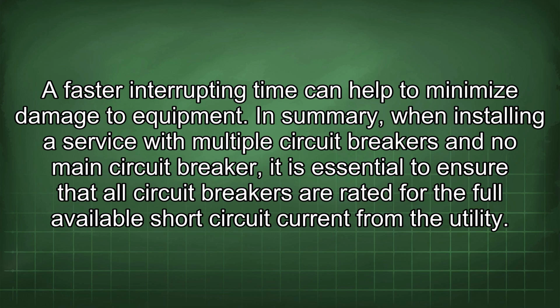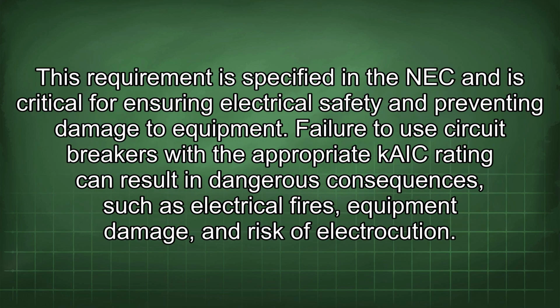In summary, when installing a service with multiple circuit breakers and no main circuit breaker, it is essential to ensure that all circuit breakers are rated for the full available short circuit current from the utility. This requirement is specified in the NEC and is critical for ensuring electrical safety and preventing damage to equipment. Failure to use circuit breakers with the appropriate kAIC rating can result in dangerous consequences such as electrical fires, equipment damage, and risk of electrocution.